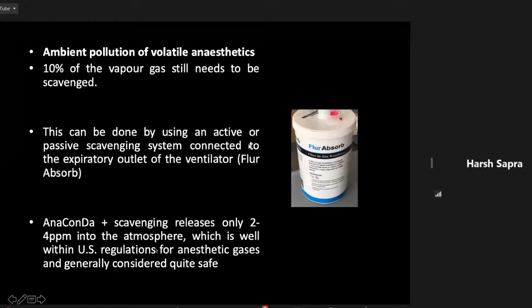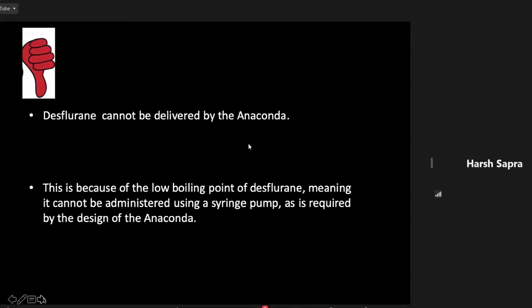Desflurane cannot be delivered by the Anaconda. This is because of the low boiling point of desflurane, meaning it cannot be administered using a syringe pump, as is required by the design of the Anaconda. So for that, we have another device called the Mirus.